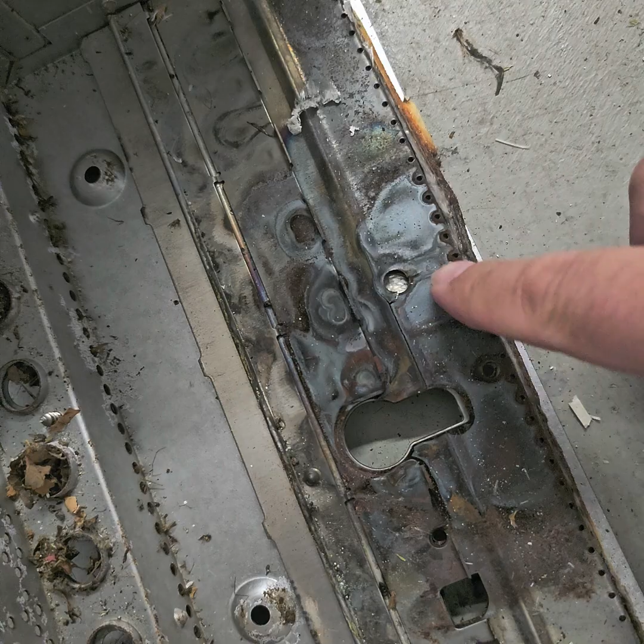More importantly, now this is the front of the unit. You see where it has been superheated. Yes, the metal is actually starting to get crunchy. It's actually cracked here and cracked there. And that is not from us taking it apart. That is actually the unit being cracked. So I always let everybody know, maintenance on tankless water heaters is very important. Your overall life expectancy on a tankless should be 20 plus years, okay? You should make sure that you're maintaining it. I have people that say 10 to 12 years for a tankless water heater, but we've always exceeded that life expectancy with proper maintenance and cleaning.